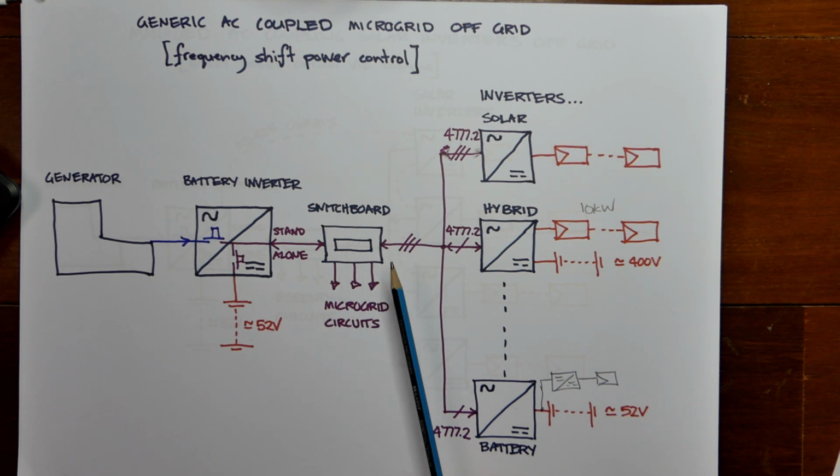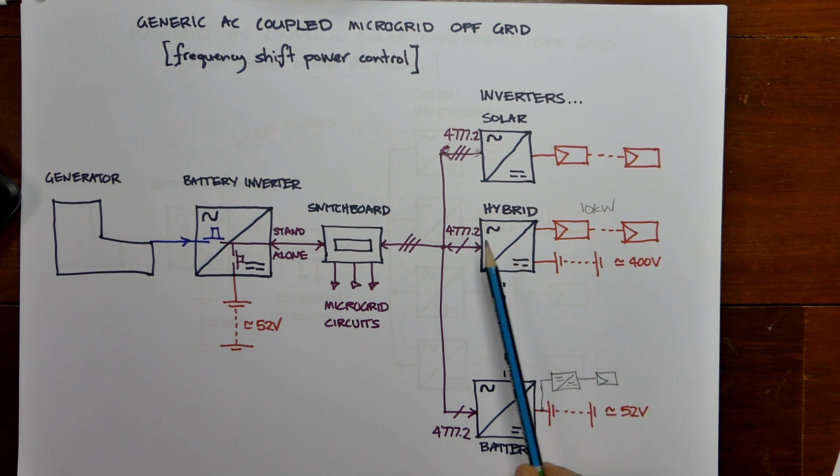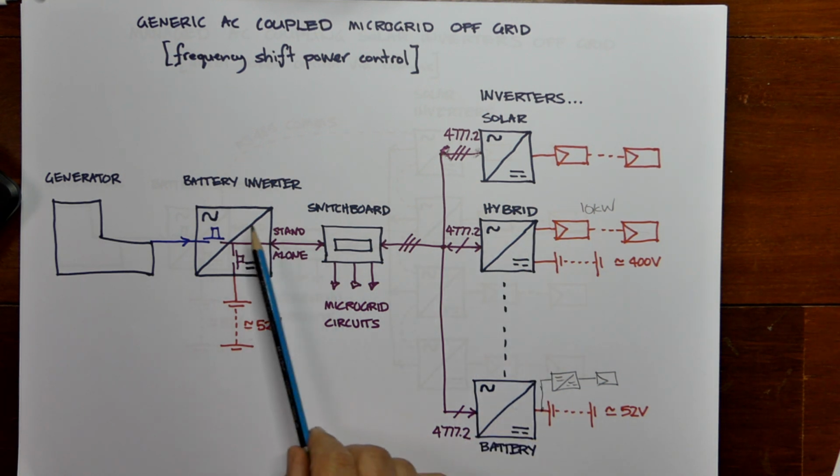So in a way, efficiency doesn't matter if you have surplus. If you've got surplus energy, you might as well do what you like with it, whether it's charge batteries, supply loads, or, as we'll get to in a minute, have discretionary loads that you can turn on and soak up some of that surplus. But I agree with Kieran, you don't really want to charge one battery to charge another battery as the normal step. You actually want to use that battery to buffer demand. So we're not designing the system so that this hybrid inverter charges up this battery during the day and then charges up this battery during the night. It would be two losses, but they're not huge. 5% and 5%, you've got 10% loss there.